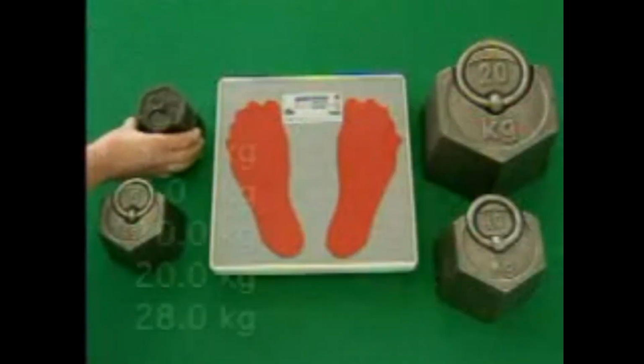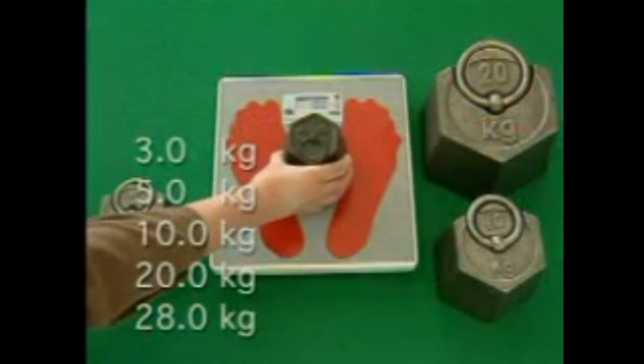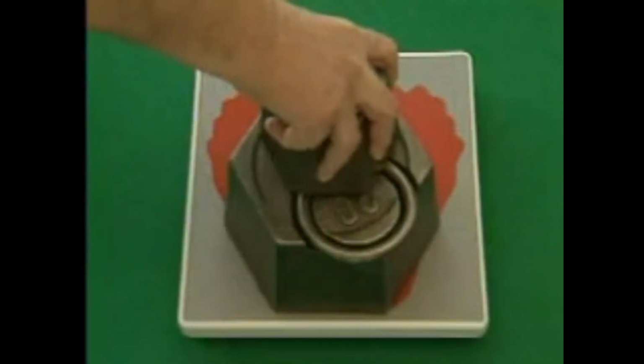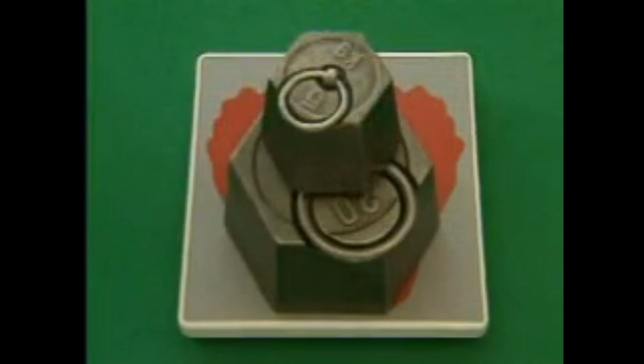All equipment must be stored safely, and its accuracy must be maintained consistently. Accuracy checks should be performed at the time of purchase or upon receiving new equipment and should be verified weekly. Weighing scales use weights of known values, for example, 3 kilograms, 5 kilograms, 10 kilograms, or 20 kilograms. To ensure the scale reads accurately, for example, placing a known 3 kilograms weight on the scale should yield a reading of exactly 3 kilograms.